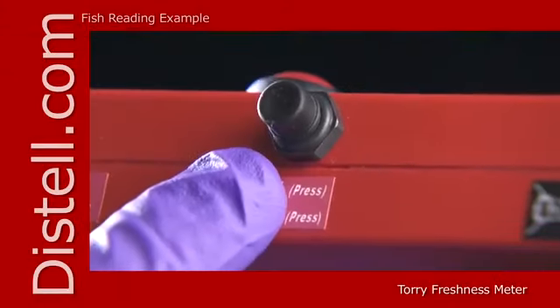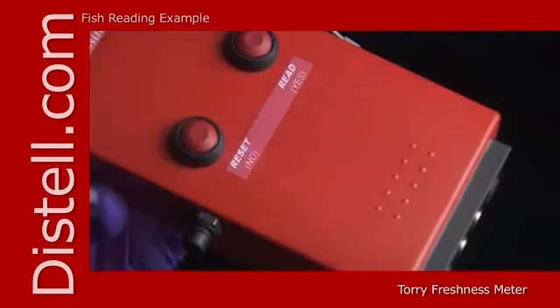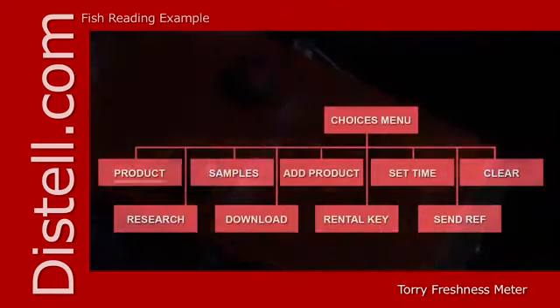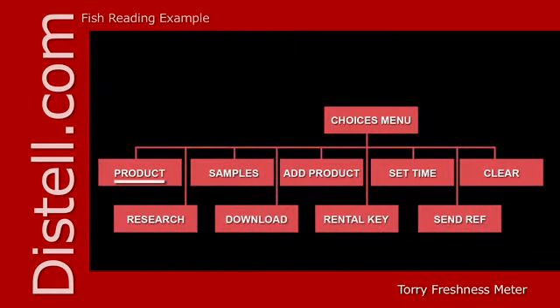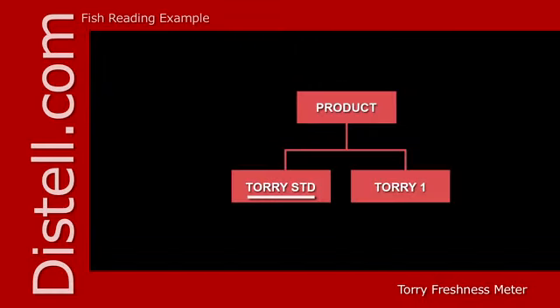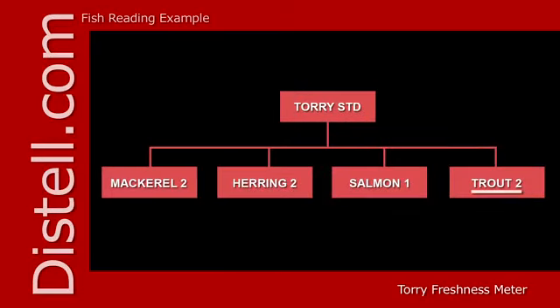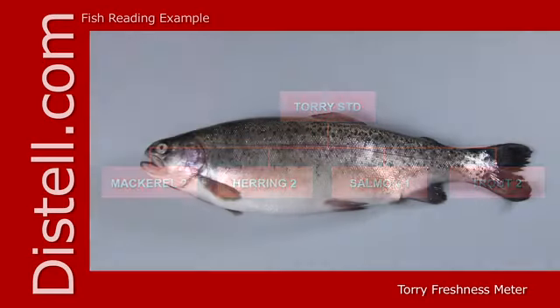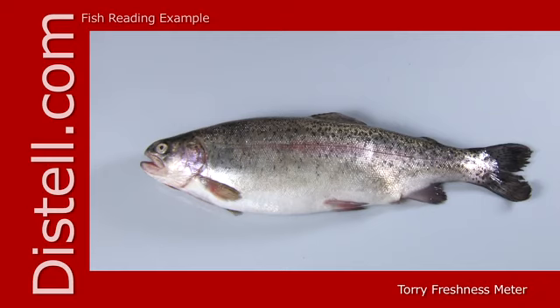Having switched the meter on, you can proceed to take measurements. Choose the correct setting from the Product function menu, in this case, Torry Standard. In this example, we are using a trout fish sample. In most cases, 3 readings from the same point are taken to obtain the freshness value.